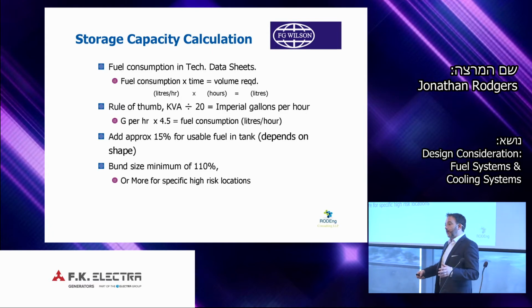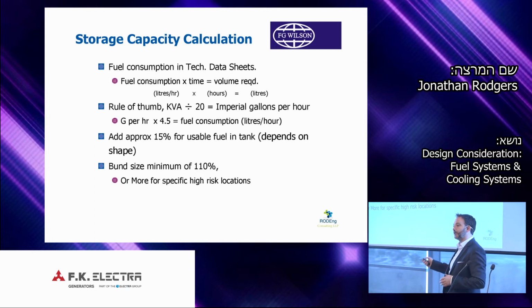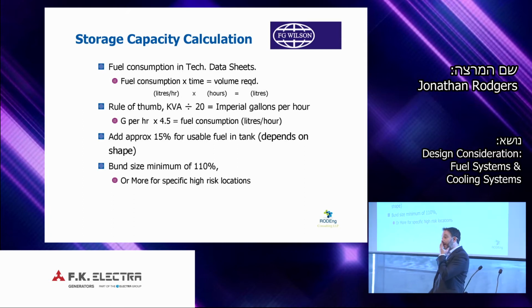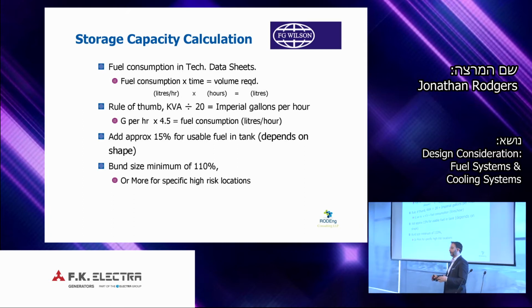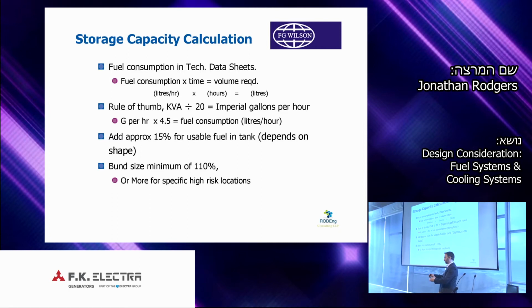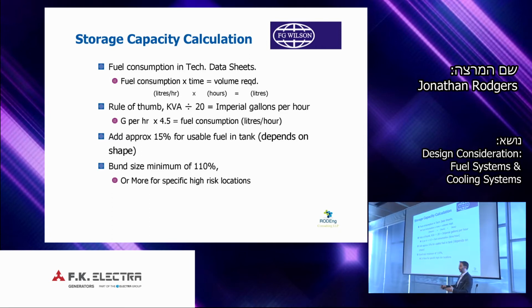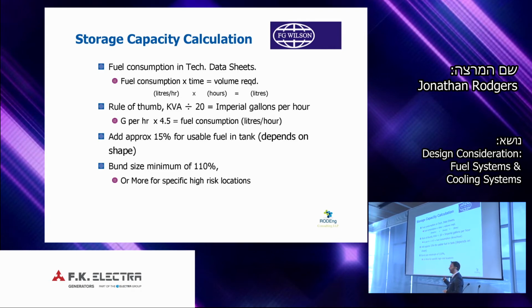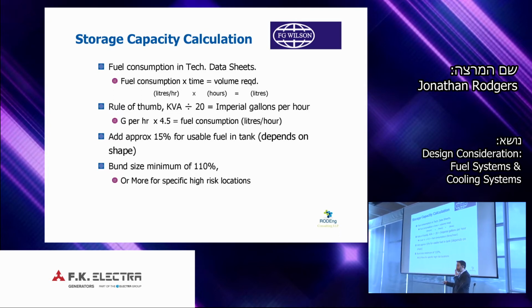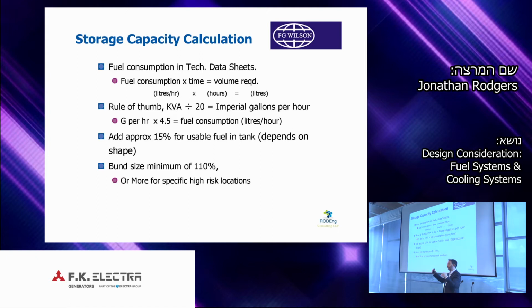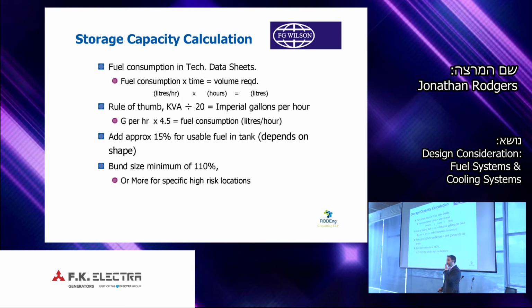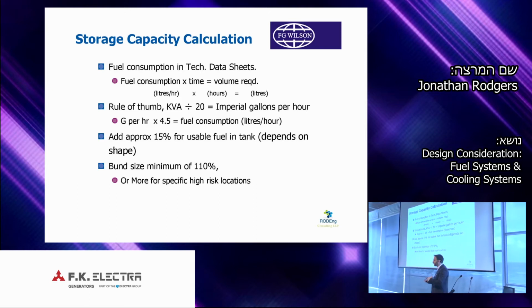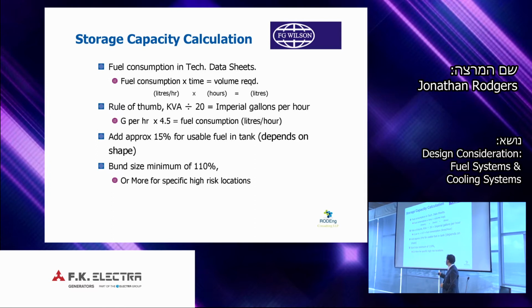Depending on local requirements or specific applications, this bund volume may need to increase. So for example, if it's an environmentally sensitive area, maybe a fuel installation offshore or near a river or a waterway, this bund level may need to increase by an additional 5 or 10%. And also if the bund is open to the environment where there can be rainwater and you need to separate, you'll be looking at an additional 10% on the bund for that. So that'll be within local regulations, but they tend to be typically the same values.